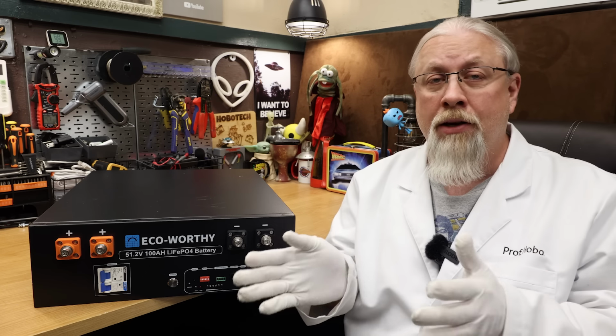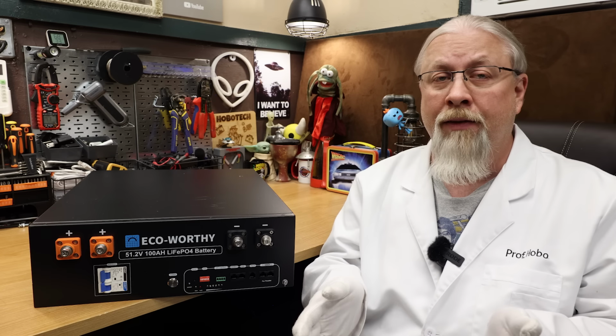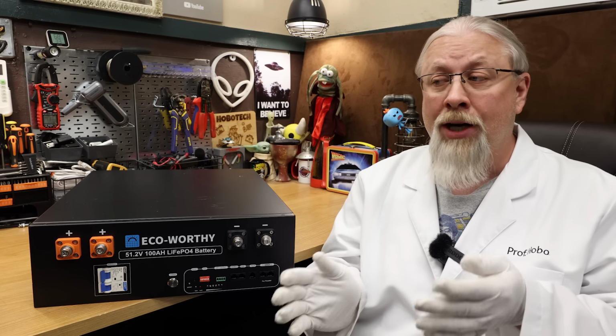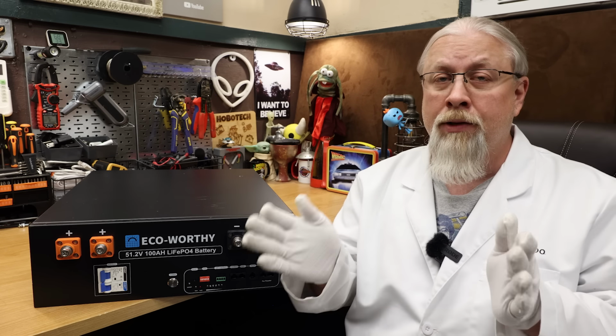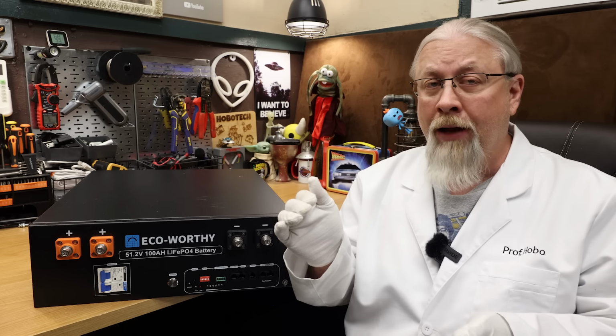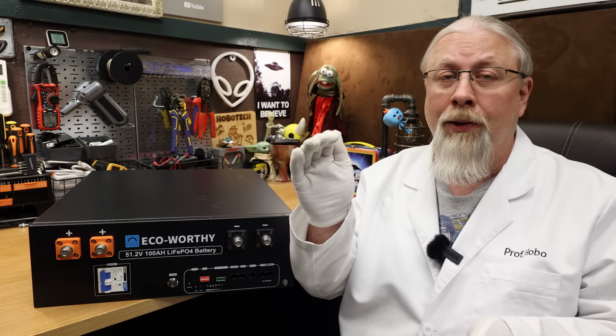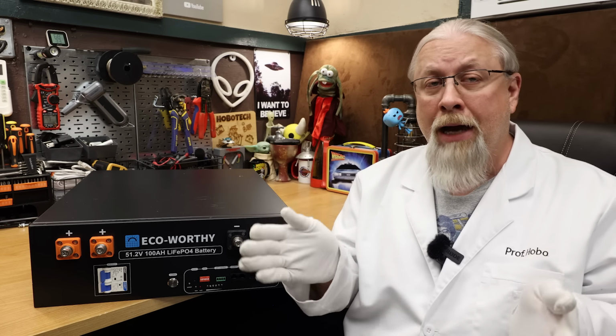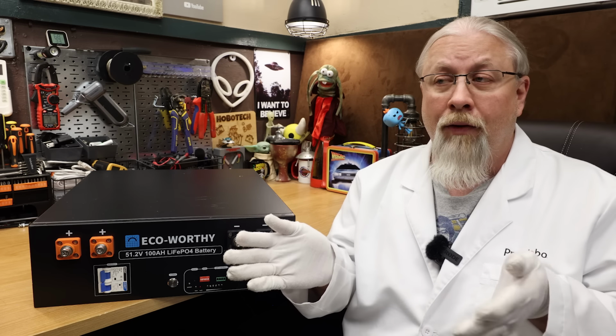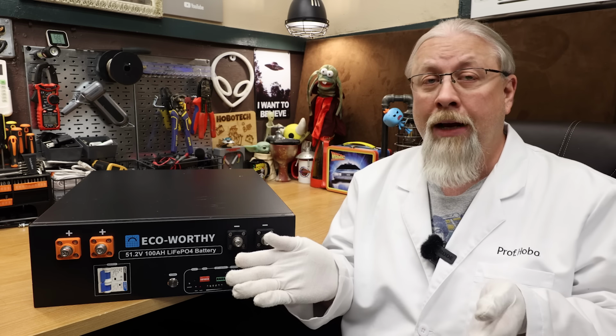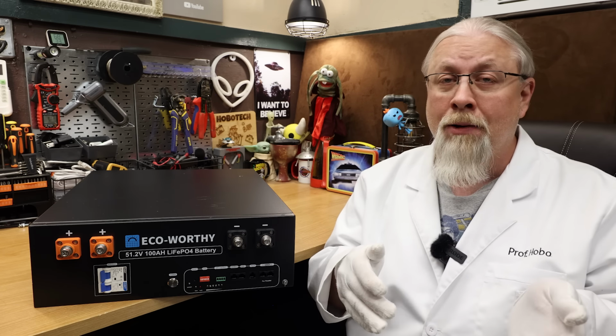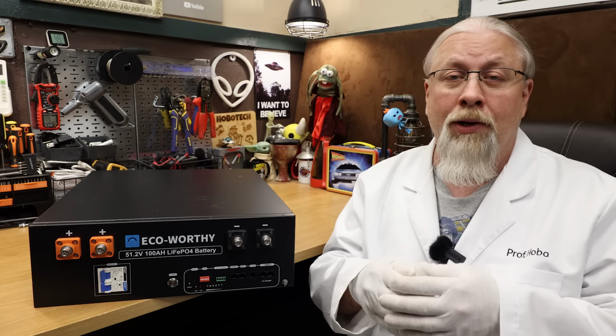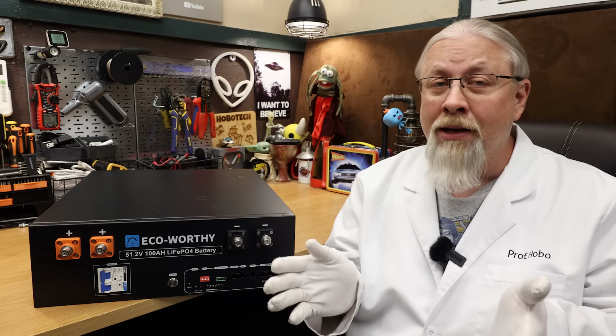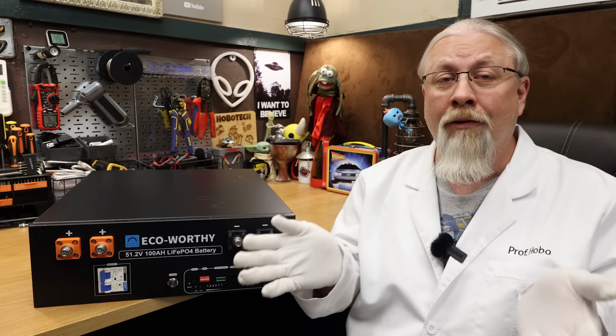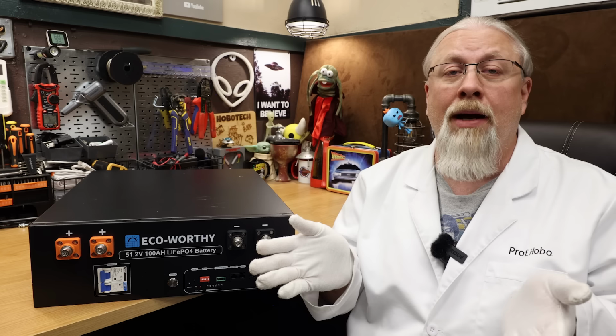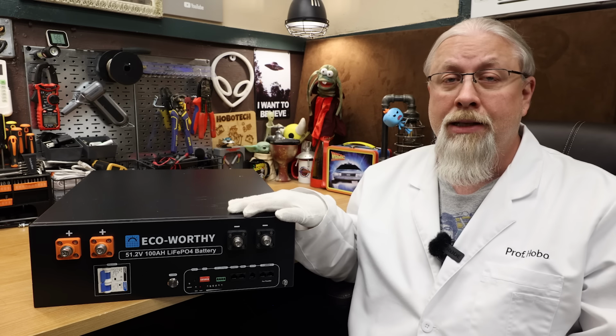This is the current standard for server rack batteries in 2025, but note that some older models were actually 48 volts nominal. There's a big difference between the two, because you can't pair up a 48 volt nominal with a 51.2 volt nominal. You can tell immediately which is which by the battery's rated watt hour capacity: if it's 4,800 watt hours, it's a 48 volt battery; if it's 5120 watt hours, it's a 51.2 volt nominal. These different batteries use different numbers of cells in series and therefore require different charger settings, so keep this in mind if you plan on adding this battery to an existing battery bank.